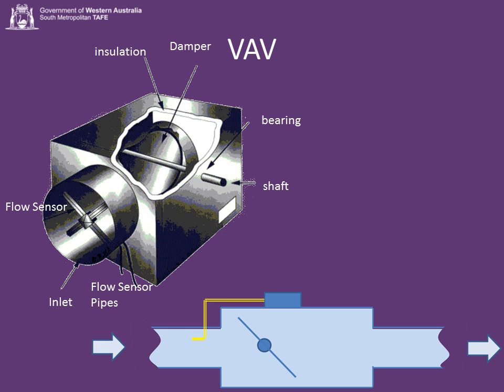You have an airflow sensor, normally a pitot tube of some description. What the airflow sensor does is it senses the airflow. It actually measures air speed, let's be honest. It's measuring the velocity of the air. And from the velocity of the air and the fact that we know the diameter of the duct, you can calculate the airflow. So you open and close the damper to increase or decrease the airflow through the VAV.